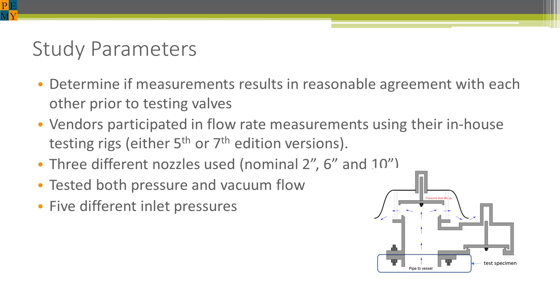Three different nominal nozzle sizes were used, 2 inch, 6 inch, and 10 inch. The test was conducted under both pressure and vacuum flow modes or conditions at five nominal inlet test pressures.